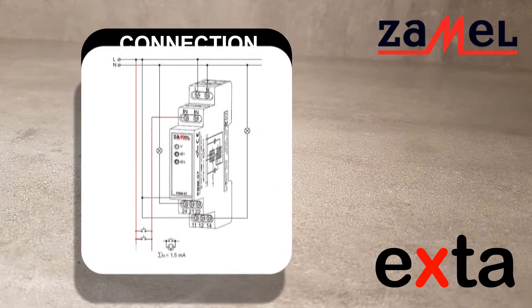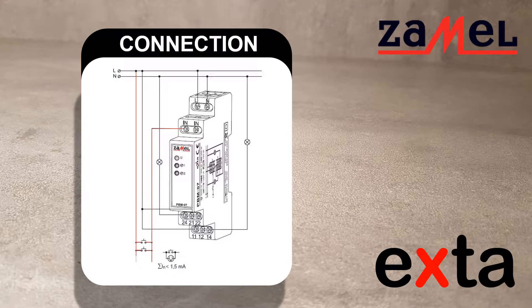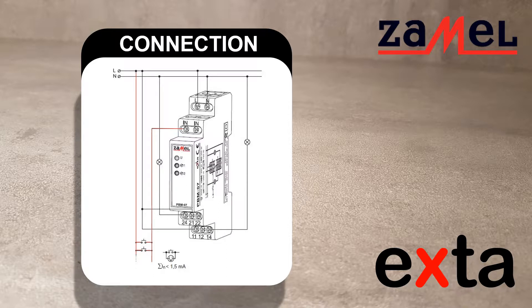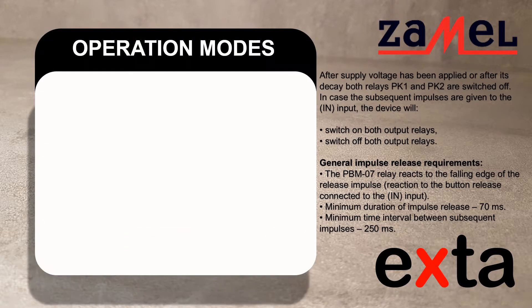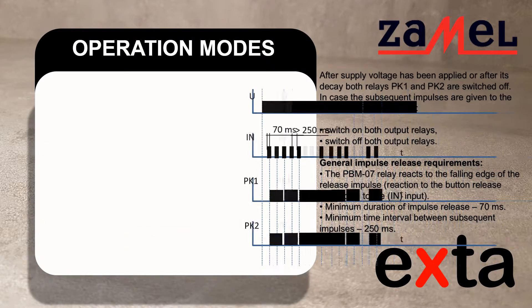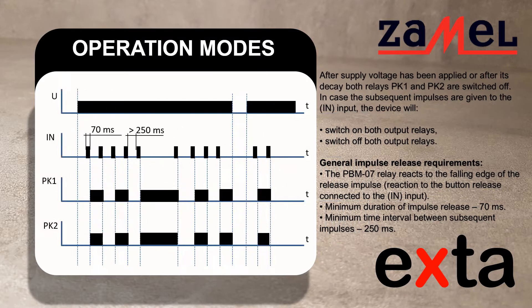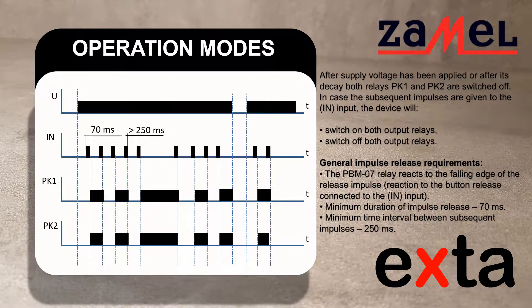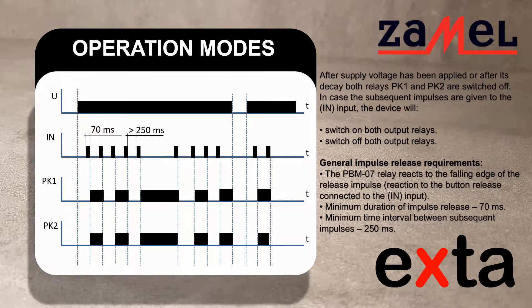Control impulse must be the signal coming from the L line. The design of the trigger input enables to work with backlit buttons, even with LED backlight. The total current from the backlight cannot exceed 1.5 milliamps. The device is prepared for installation in switchgear on the TH35 rail.